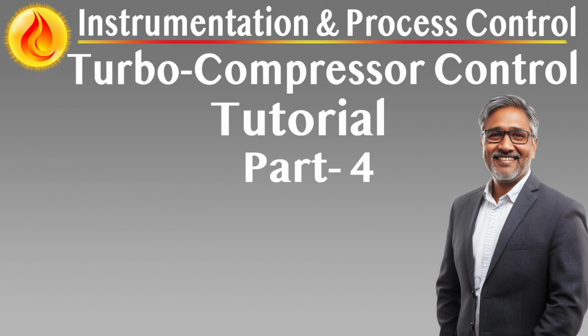HMI graphical display package. Standard display set includes overview screen for each compressor train, turbine performance map, and live speed power curves. Compressor stage maps with surge line and real-time operating points, lube oil and seal gas systems displays, anti-surge controller and valve displays, load sharing and performance controller interface, vibration and temperature trend panels, alarm summary, first out alarms, and history, system diagnostics and test reports, manual command and maintenance access pages, help and document access area. All displays are configurable and new graphic pages can be added post-commissioning.